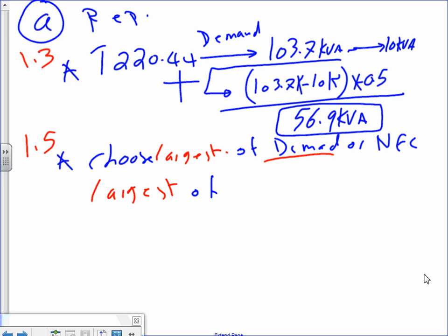You take the part you subtracted and leave it alone. That part of the calculation, they do not want you to touch it. Does that make sense? The 10 kVA here, this is how the code works, guys. They take a certain amount and say that regardless of what you do, they don't want you to go lower than this, for safety. Anything higher, cut it, right? But then at the end, don't forget the amount you left aside and add it back. Am I making sense? One more time. Yes, sir, round to the first decimal digit. That's more than what you need. So you take it off and you put it back. Absolutely. After you apply the 0.5, you're going to see a lot of monkeying like this in the code. You've got to get used to it, guys.